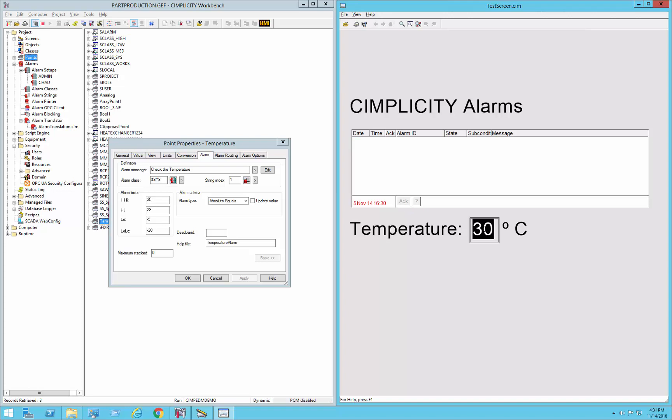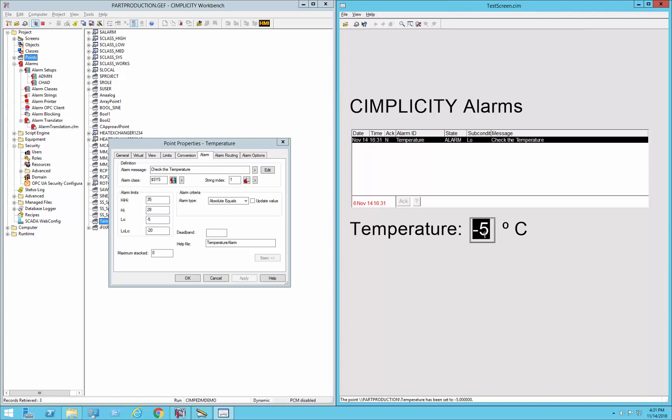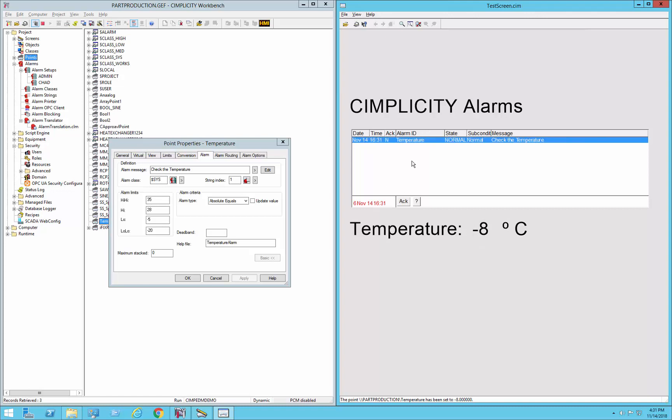But if I specifically say my value is minus 5, you can see it'll go into the low state because that exactly matches minus 5. Same thing if I go down to minus 20. It's in low low, but if I go to minus 8, that's not an alarm, that's normal. And that can be taken out of alarm. So that is absolute equals alarm.